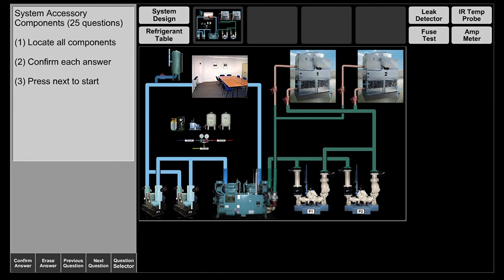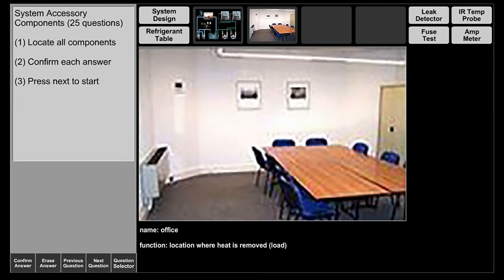We're going to be discussing the reciprocating chiller system and its components — a basic review of the cycle and the responsibility of each component. The main idea is to cool down this room. This room has an air handler, which is a coil with a fan, controlled by a thermostat. Once set to a standard temperature such as 69 to 72 degrees Fahrenheit, it allows chilled water to circulate, and the fan blows over the coils, allowing cold air to come in while recovering heat to be dissipated at the chiller system.